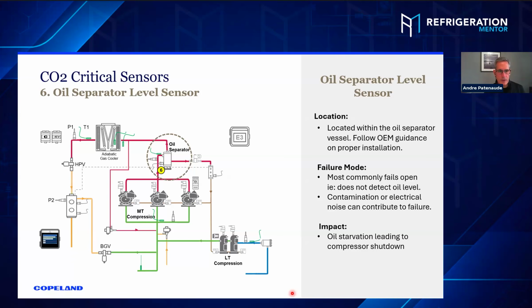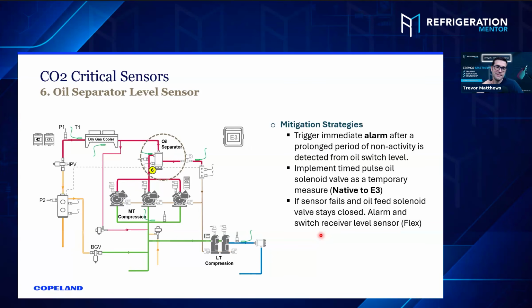Number 6 out of 8, oil separator level sensor. Most commonly fails open, doesn't detect oil. So again, you might have some contamination or something else that's caused the low level control to fail. And the impact would be oil starvation leading to compressor shutdown. Yeah. So if that particular sensor fails, you'll trigger an alarm when there's a period of non-activity, because you don't know it's failed. You just know that you're not getting any activity. The solenoid valve's not energizing to fill the reservoir up.